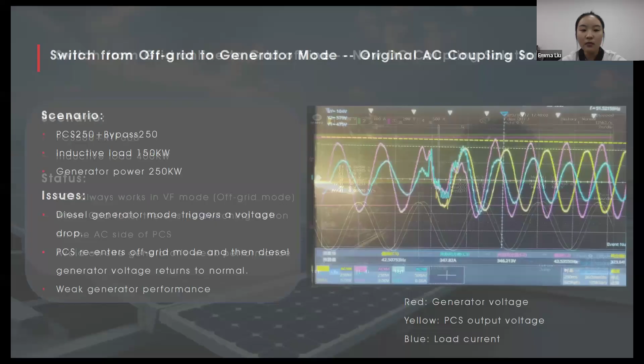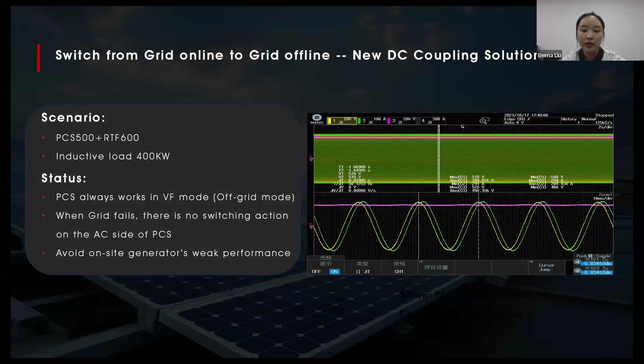PCS always works in off-grid mode. When grid fails, there's no switching action on the AC side of PCS. We can surely avoid on-site generators with weak performance or unstable grid. It's just like an online UPS solution.